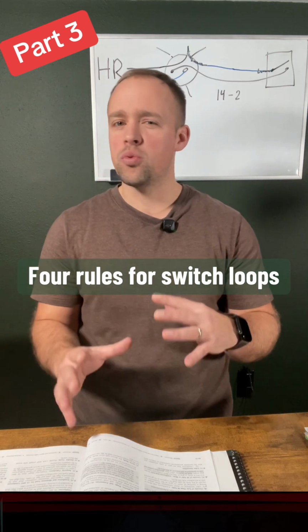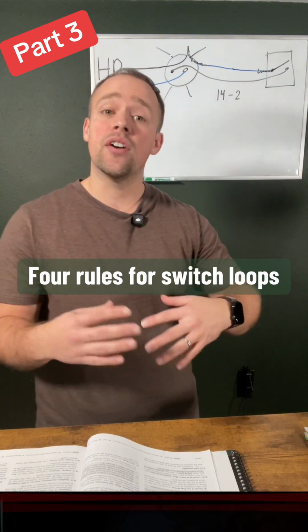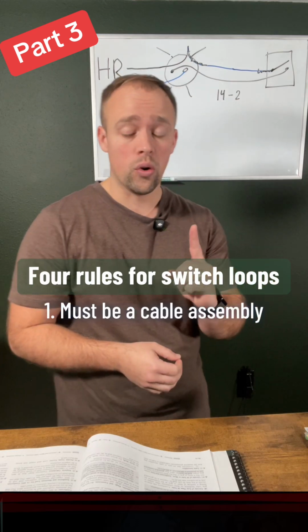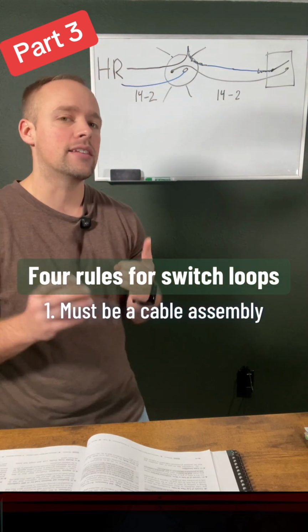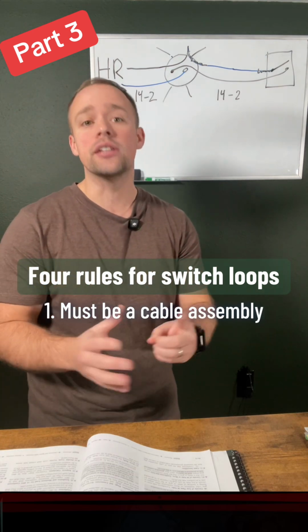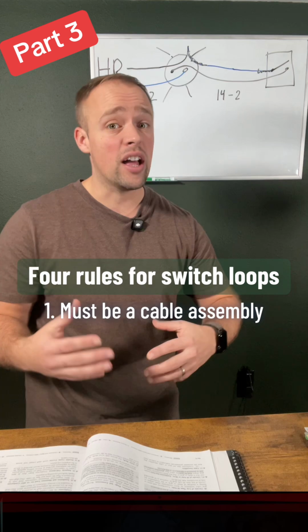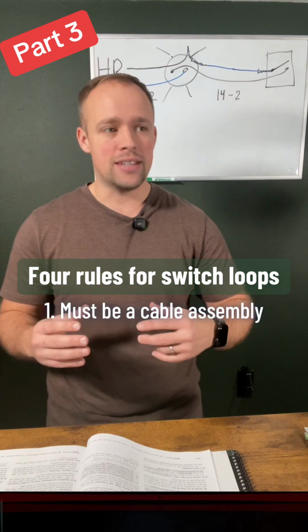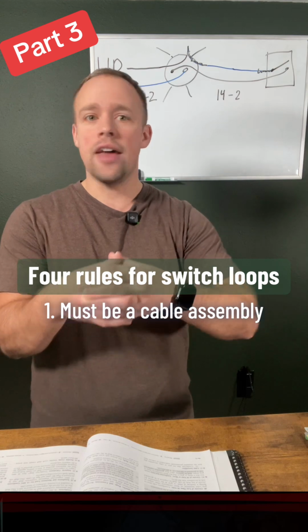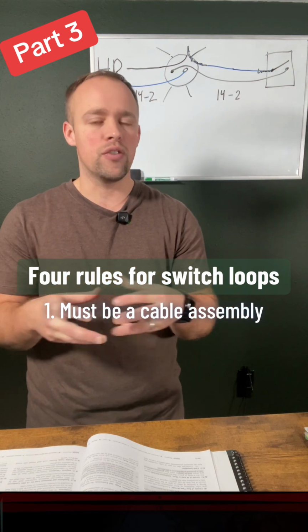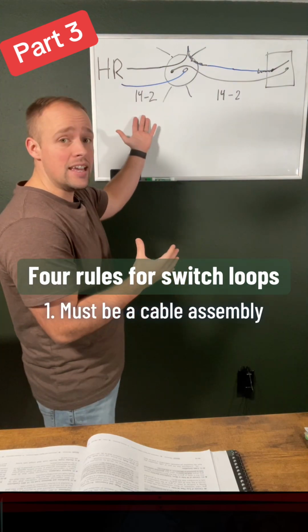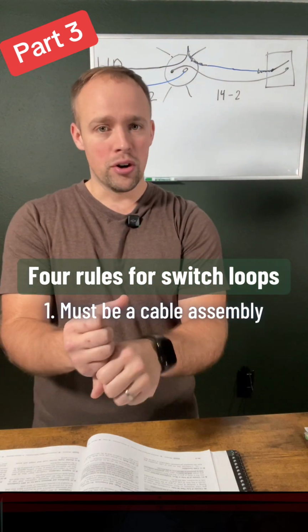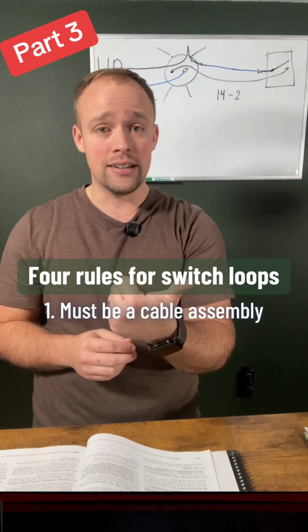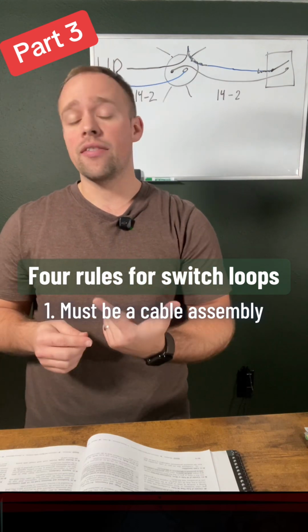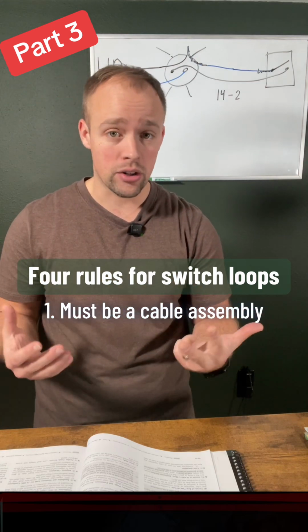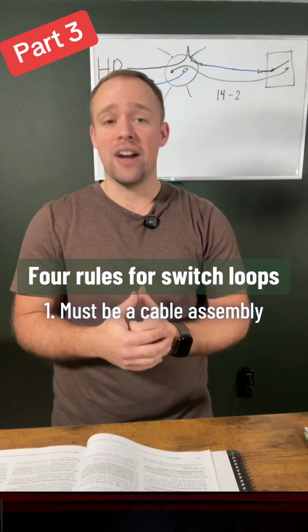Like, I don't think there's too much wordplay going on here, but again, I think it's very easy to look over these rules. So the first rule that I want to identify is the fact that it's only allowed in cable assemblies. What is a cable assembly? Okay, something like Romex or MC cable is a cable assembly that you purchase in the store, and all the wires are assembled in it. Okay, so if you buy 14/2, for instance, like we have in this diagram, you purchase it, you strip the sheathing, and you have a black conductor, ungrounded, your white, your grounded, and then your bare, which is your grounding conductor. Okay, they're already assembled by manufacturer's design.